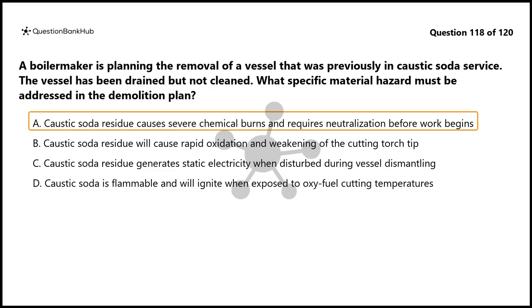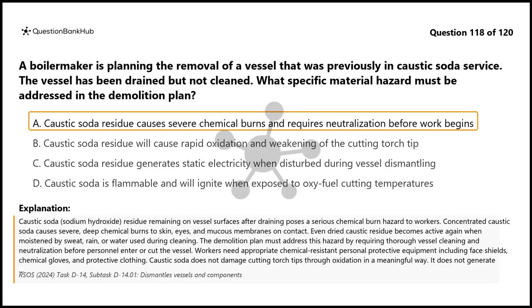The correct answer is A. Caustic soda, sodium hydroxide, residue remaining on vessel surfaces after draining poses a serious chemical burn hazard to workers. Concentrated caustic soda causes severe, deep chemical burns to skin, eyes, and mucous membranes on contact. Even dried caustic residue becomes active again when moistened by sweat, rain, or water use during cleaning. The demolition plan must address this hazard by requiring thorough vessel cleaning and neutralization before personnel enter or cut the vessel. Workers need appropriate chemical-resistant personal protective equipment including face shields, chemical gloves, and protective clothing.